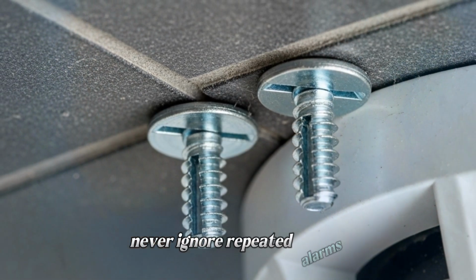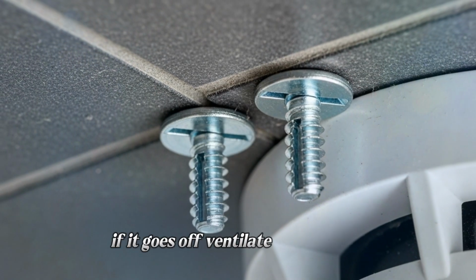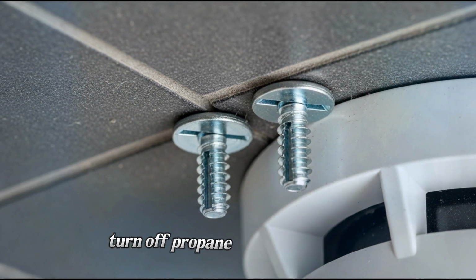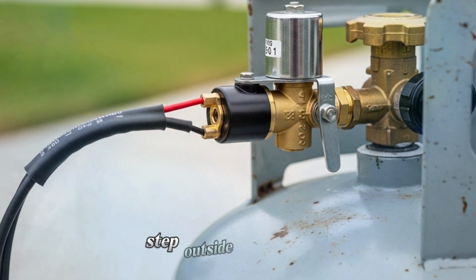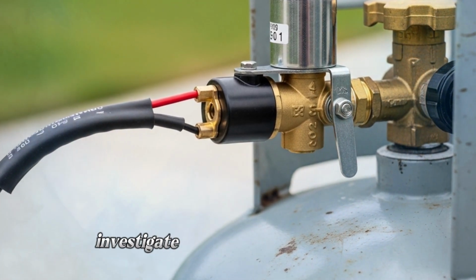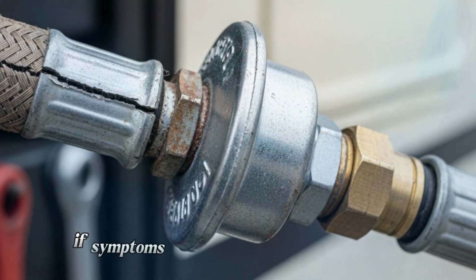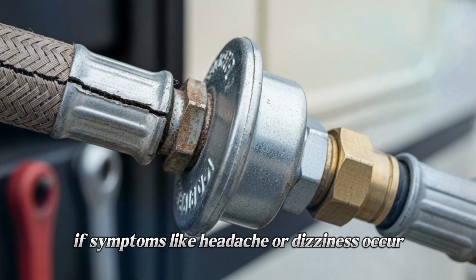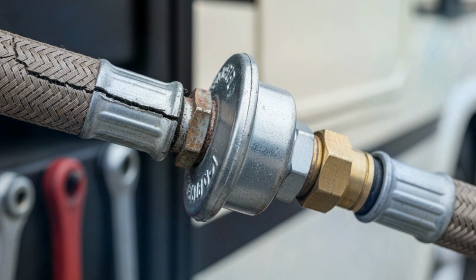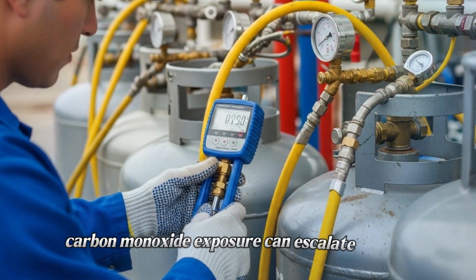Never ignore repeated alarms. If it goes off, ventilate immediately. Turn off propane supply at the tank. Step outside for fresh air. Investigate only after the space is safe. If symptoms like headache or dizziness occur, seek medical help immediately. Carbon monoxide exposure can escalate quickly.